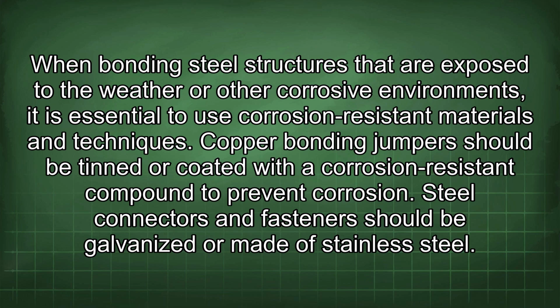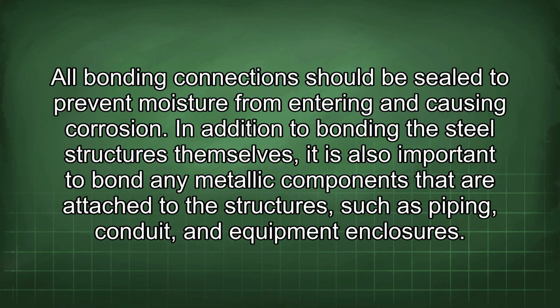Copper bonding jumpers should be tinned or coated with a corrosion-resistant compound to prevent corrosion. Steel connectors and fasteners should be galvanized or made of stainless steel. All bonding connections should be sealed to prevent moisture from entering and causing corrosion.